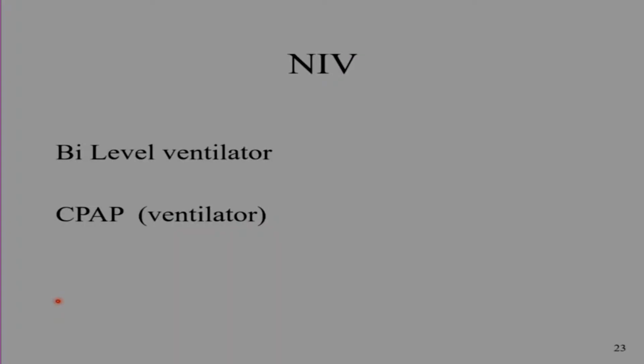For the next few slides, I just want to say a few words about ventilators. If you look at non-invasive ventilators, there are two types. One is a bi-level ventilator, which has different pressure or volume in inspiration and expiration. The second one, which you may or may not call a ventilator, is a CPAP machine - continuous positive airway pressure, meaning a continuous pressure.